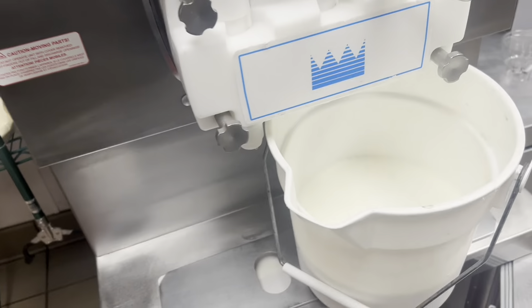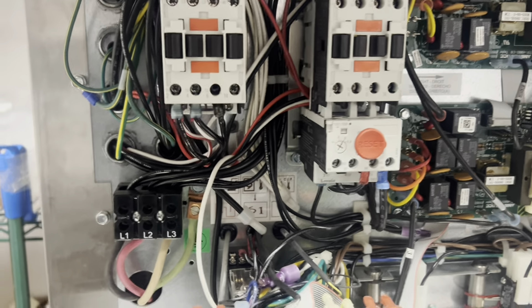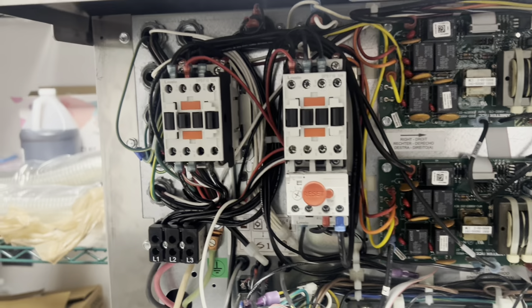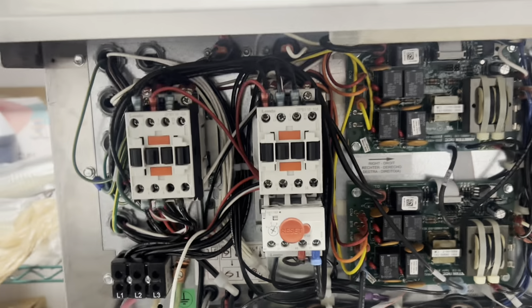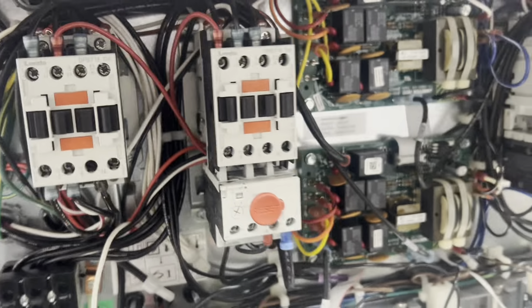What I'm doing is before I replace this contactor, I'm actually going to run a test first. I'm really torn because one of you made a great point — these Lovato contactors have a much heavier duty contact in there for all the on-offs that it does. There's a reason this costs more than a regular old three-pole contactor.